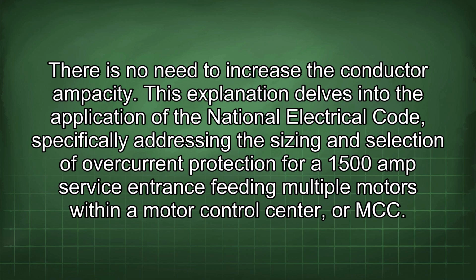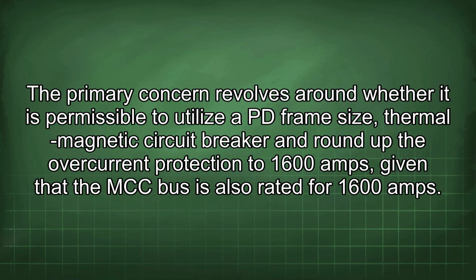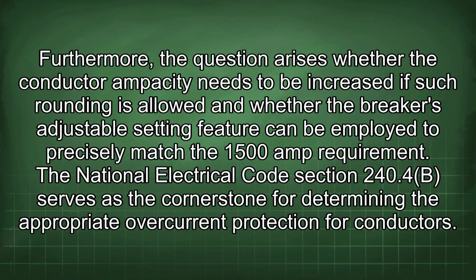This explanation delves into the application of the National Electrical Code, specifically addressing the sizing and selection of overcurrent protection for a 1500 amp service entrance feeding multiple motors within a motor control center, or MCC. The primary concern revolves around whether it is permissible to utilize a PD frame size thermal magnetic circuit breaker and round up the overcurrent protection to 1600 amps, given that the MCC bus is also rated for 1600 amps. Furthermore, the question arises whether the conductor ampacity needs to be increased if such rounding is allowed and whether the breaker's adjustable setting feature can be employed to precisely match the 1500 amp requirement.